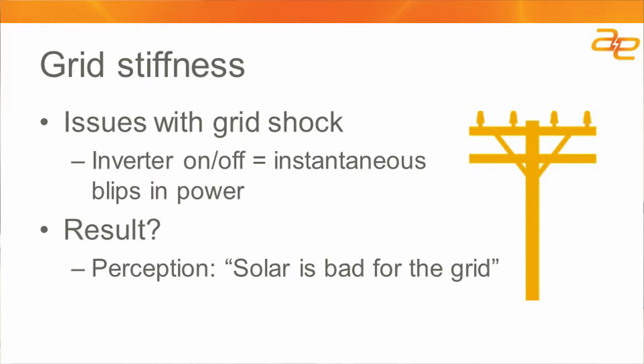So grid stiffness is an issue that has come up quite a bit in North Carolina and other parts of the country as well. There's a lot of concern that the more generation you have from these variable sources of energy like wind and solar, the more grid instability you're going to have. So there's a tiny bit of truth to the issue. If there were a large number of solar sites on the same distribution line and they were all to power up instantaneously, it would cause a little bit of a shock to the system. However, the sites are designed so that that shouldn't happen, and controls can make it so even if it were to happen, they would come online gradually and they'd go offline gradually, which would reduce or minimize the shock to the distribution system.